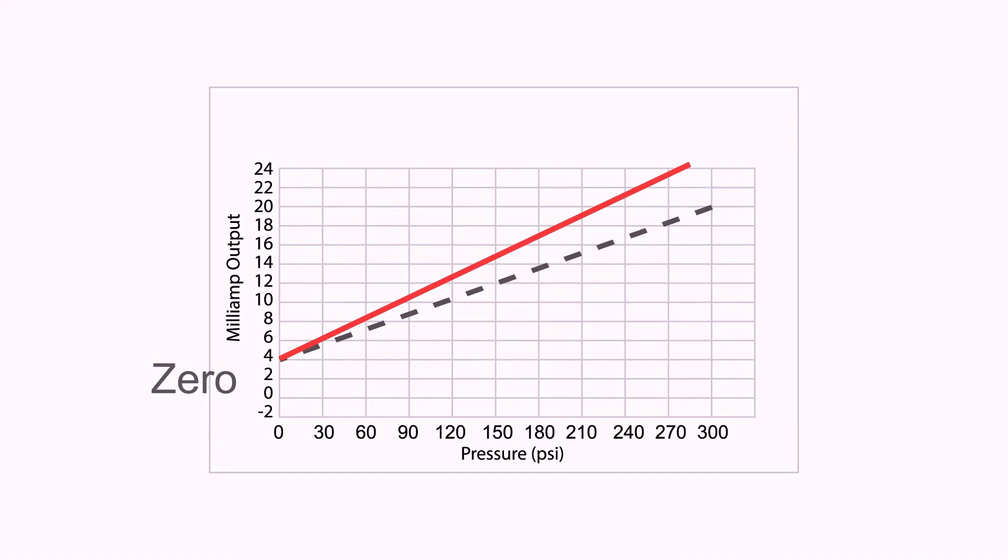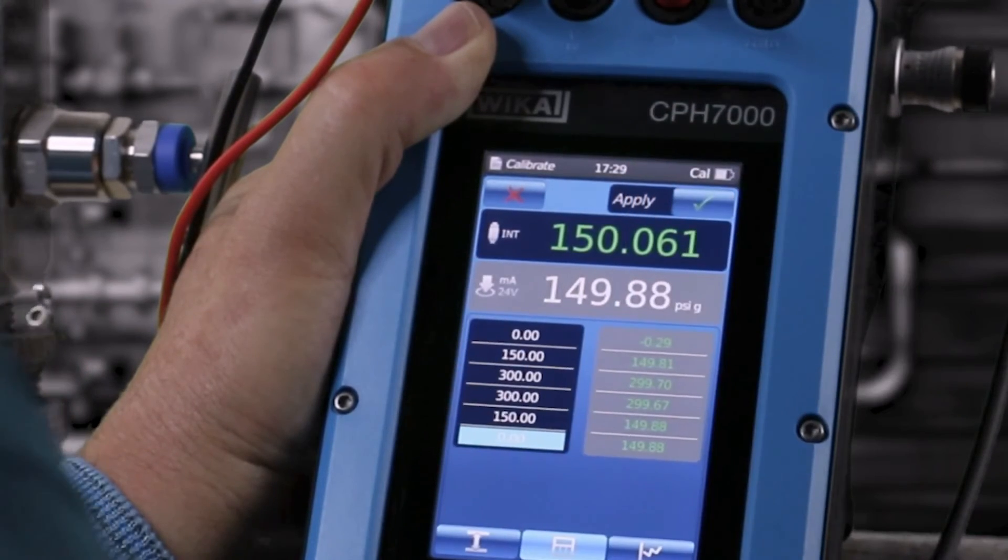If the calibration fails, then adjustments should be made to the zero and span of the transmitter to bring it within specification, and then calibrate again. The second calibration will be your as left calibration.